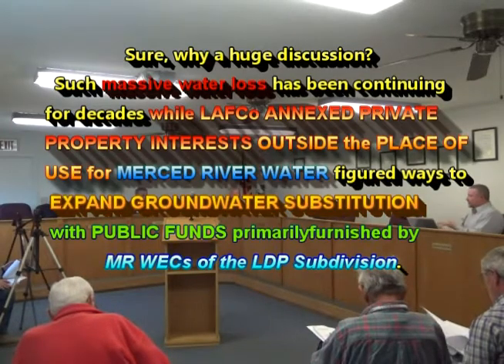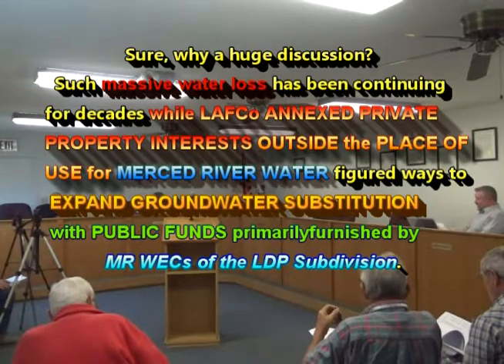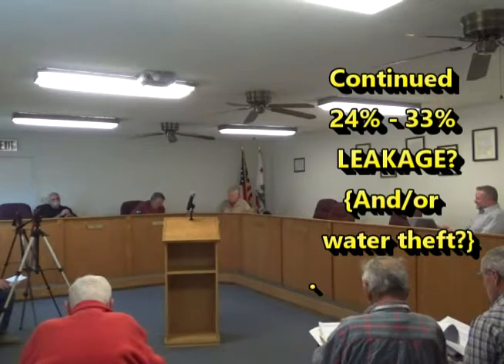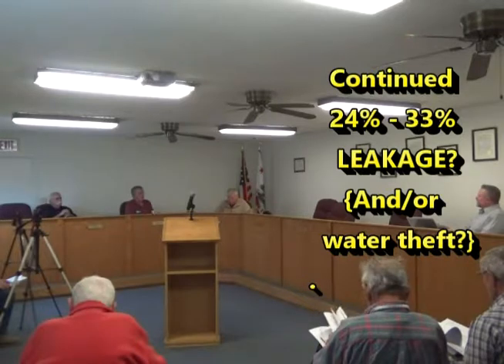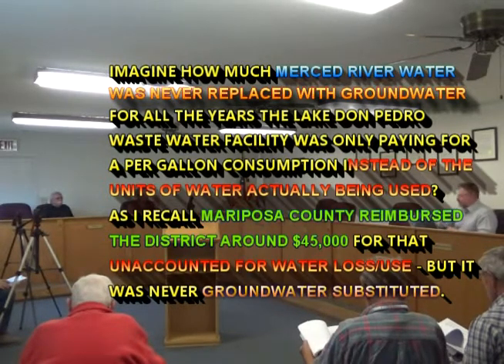And then I also updated the leak reports, not that it is a huge discussion, and we continue to see leakage somewhere between 24 and 33%, and a number of factors can contribute to that. I'm not absolutely convinced anymore that those 18 service lines are what's leaking that, but we need to give it a month to see how that reacts now, not having those two illegal connections and that other service line running. Because that could be a big chunk of that.